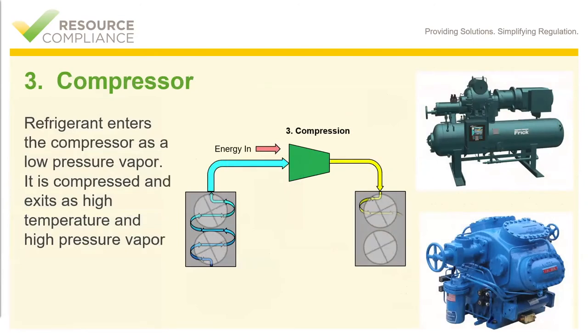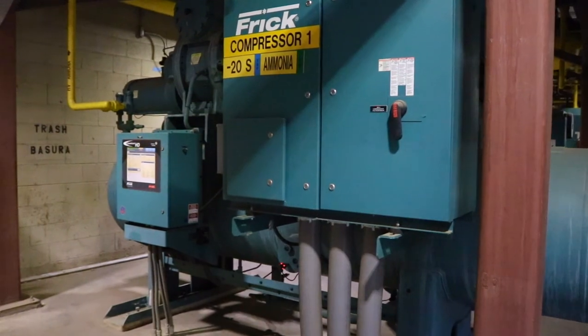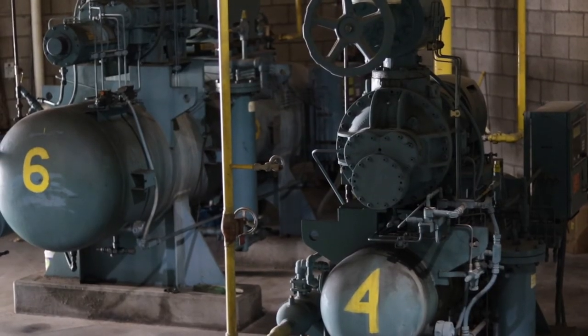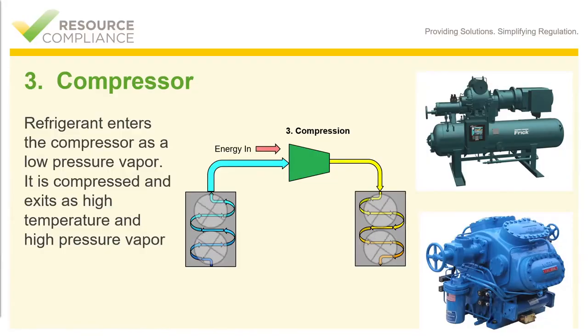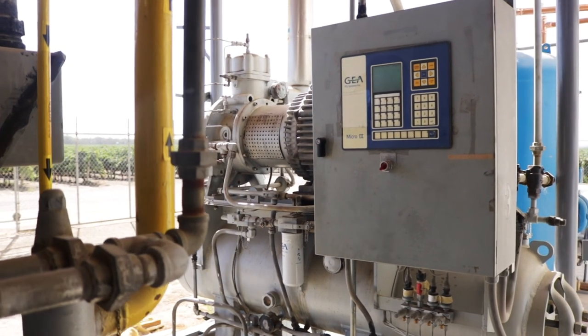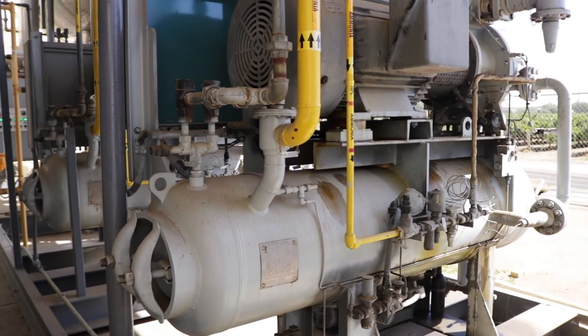Remembering that heat energy always moves from a warmer object or space to a colder object or space, the compressor in stage three serves a vital function in the refrigeration cycle. The low pressure vapor that has left the evaporative coils is still at a temperature well below the ambient atmosphere. In order to effectively reject the heat energy to the outside ambient air, we have to raise the low temperature, low pressure vapor ammonia to a high temperature, high pressure vapor. That is where the compressor comes in. The refrigerant enters the compressor as a low pressure vapor, and it is compressed and exits as a high temperature, high pressure vapor.